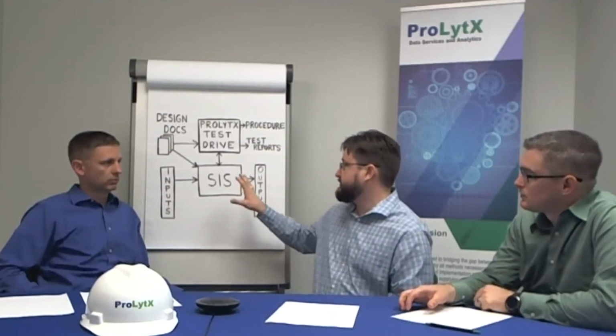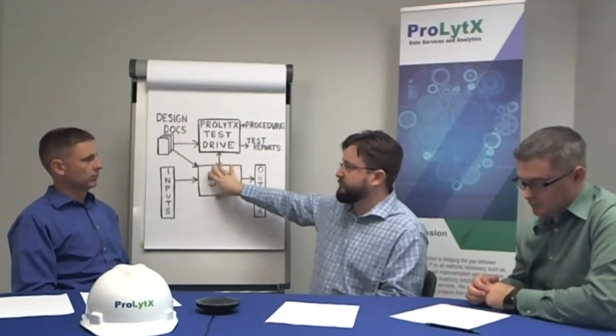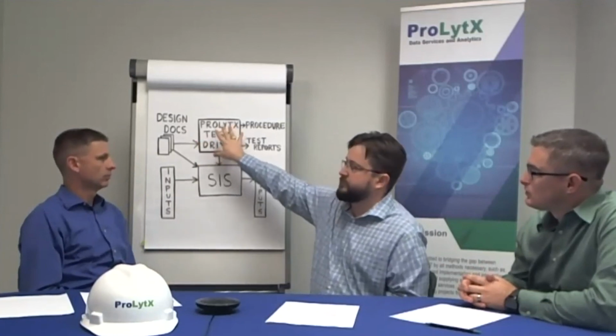So what we did is you start with the same design documents that you would start with for configuration of an SIS: your cause and effects, IO list, SRS, any narratives, everything that defines how the system is supposed to work. We take those and we produce test procedures with our software. ProLytX TestDrive is our solution. It's an SIS validation software that is procedure based. It provides a mechanism for you to create a structured test procedure, but not only that, spit that out as a document, it can also execute that in a variety of modes.